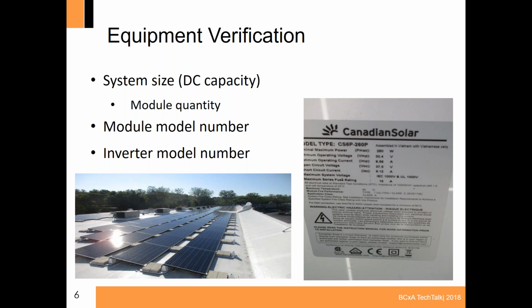Beyond that, it's going to be very difficult. But again, we look at that, and in some cases, we spot check the nameplates because we could have systems with 1, 2, 3, 4 different types of modules or different size PV modules. So that's another really important consideration here.